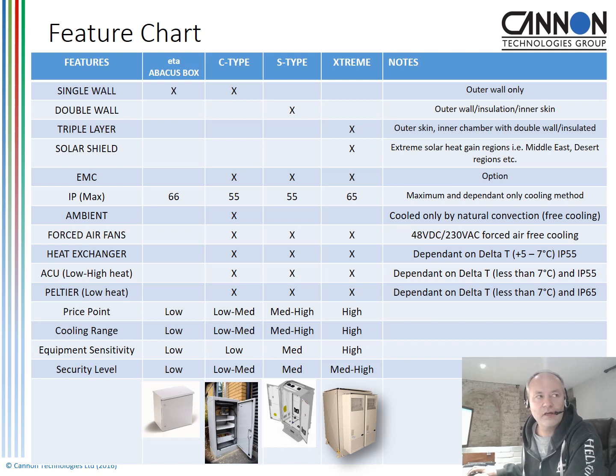IP55 is dust protected with limited ingress, which wouldn't affect the equipment, and protected against jets of water with limited ingress, obviously, which wouldn't affect the equipment. We can provide ambient cooling, so natural convection free air cooling if it's electrical equipment or very low power equipment which can operate at higher temperatures, for example 70 degrees, or we can install things like forced air active fans or heat exchangers, air conditioning units, Peltier devices, etc. And as I said, we calculate what would be required by yourselves should you have a requirement. Price point is really low to medium.